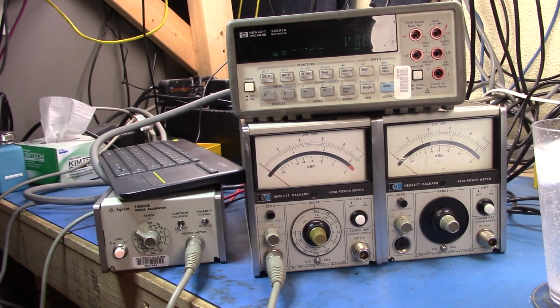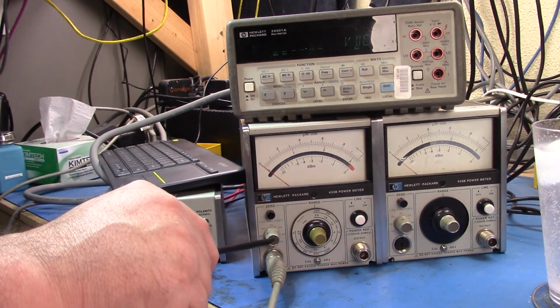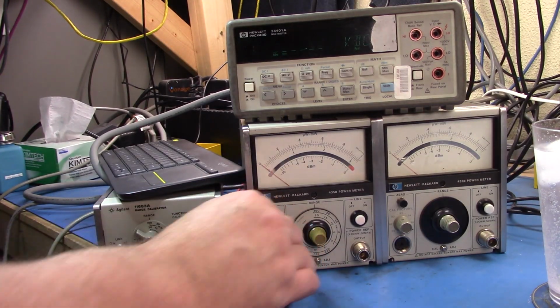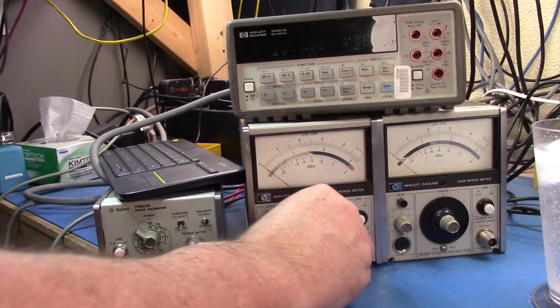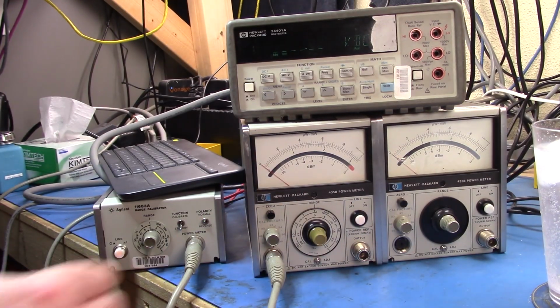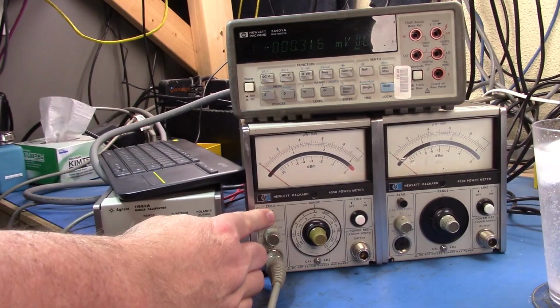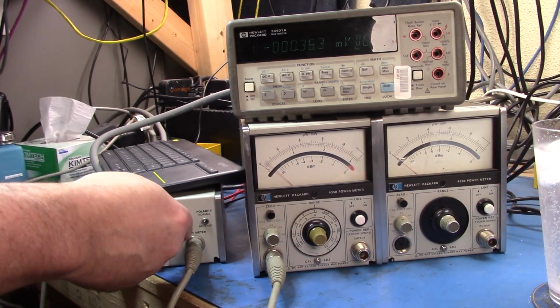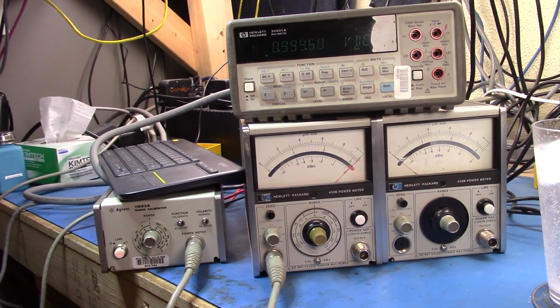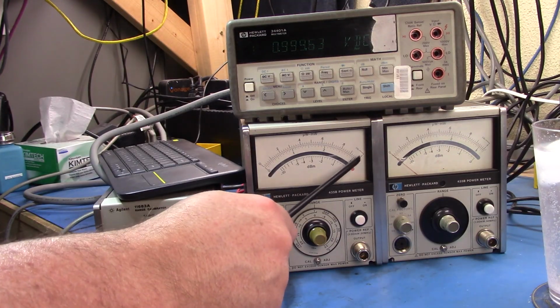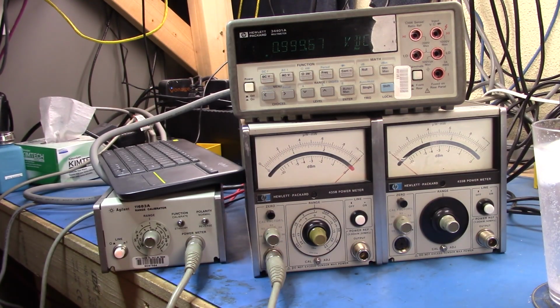So now the last step to do is to check the calibration factor here. So what I'm going to do is we'll set ourselves to 1 milliwatt and 1 milliwatt on the range calibrator. Let's go to local here. I'm going to zero that out. Okay, we'll bring that up. And you can see that from where I did the work yesterday, we're still very close to 1 millivolt. Sorry, 1 volt full scale deflection. We're at 999.6 millivolts there. So I think that's probably a reasonable position to start with.